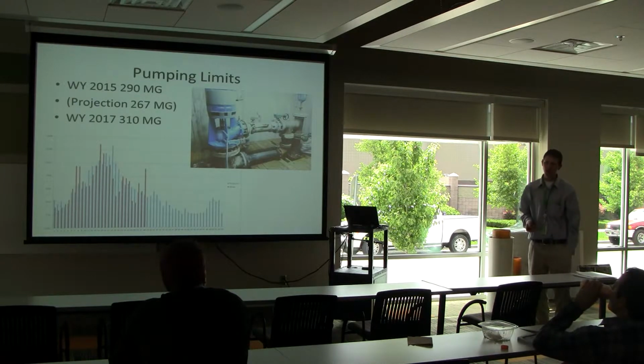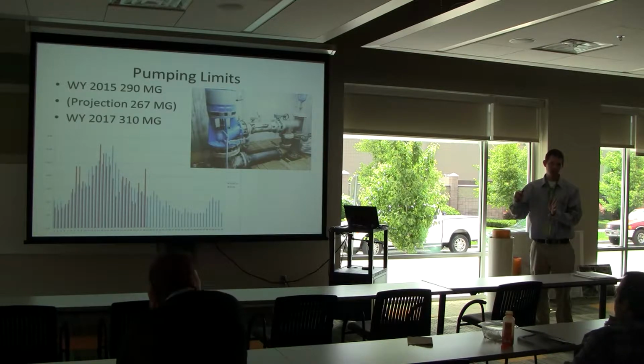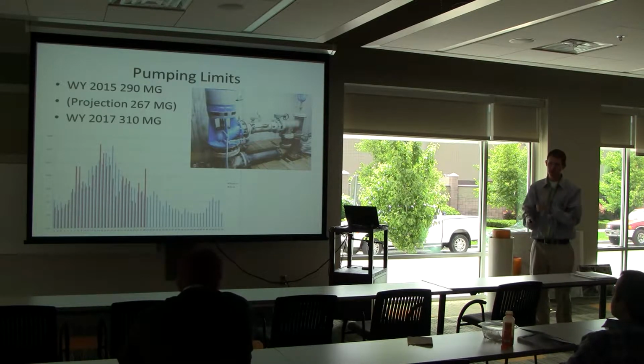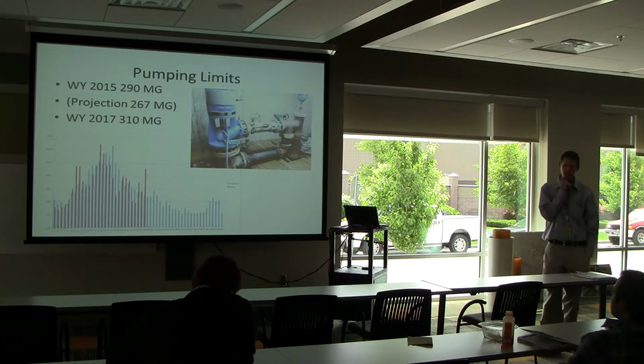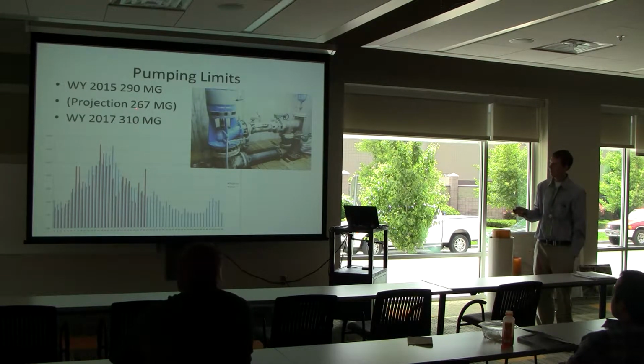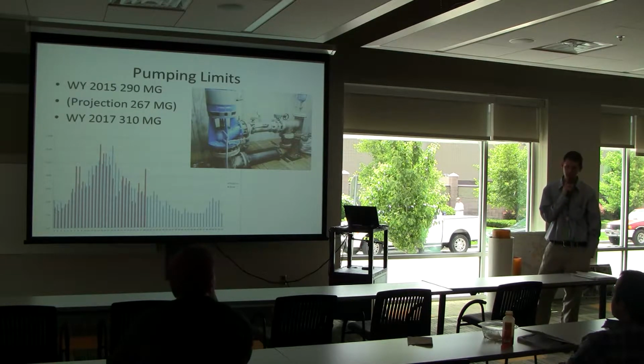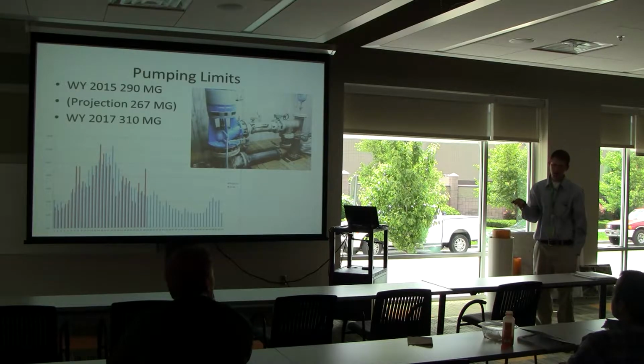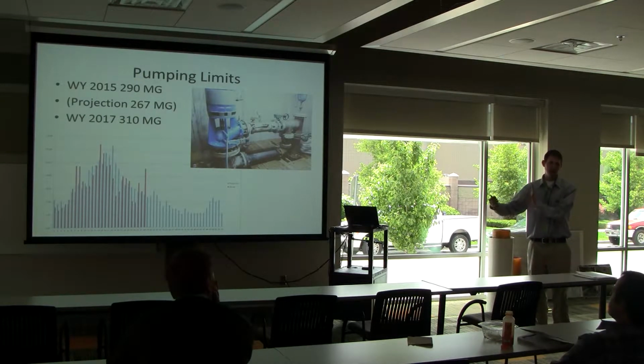On pumping limits: because of the problems in this aquifer we were given pumping limits, and we worked with all the other parties to understand them. Right now, this year, I can pump up to 290 million gallons. Even in what we called a mild winter, I'm still projecting about 270 million gallons pumped. If it had been a cold winter, I'd be right up against my limit. In fact, if I project I'm going to go over my limit, I have an agreement with Boise State that they're an interruptible customer - we can turn their water off at any time, and they have backup heat for all the buildings.